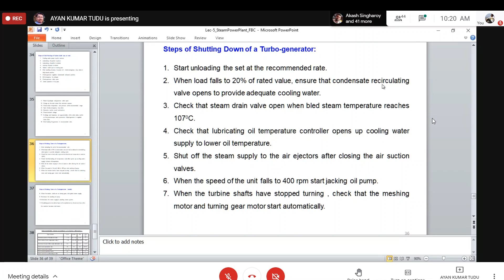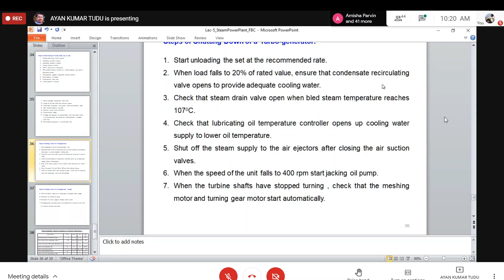When the speed of the unit, as you can see, falls to 400 rpm, we'll start the jacking oil pump. Seventh, when the turbine shafts have stopped turning, we'll check that the meshing motor and the turning gear motor start automatically. Next, when the turbine shafts are on turning gear, we'll shut the gland steam supply.